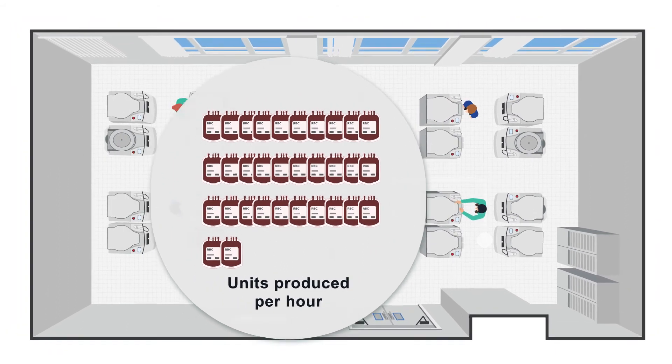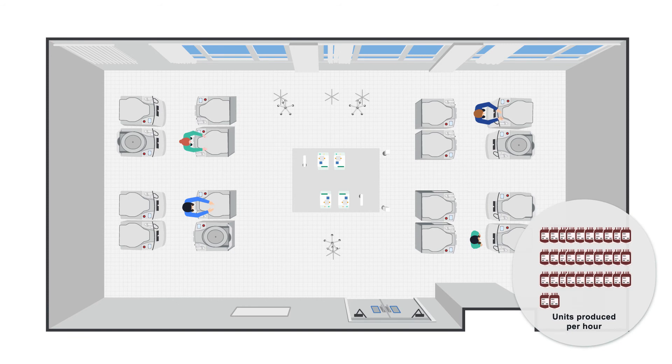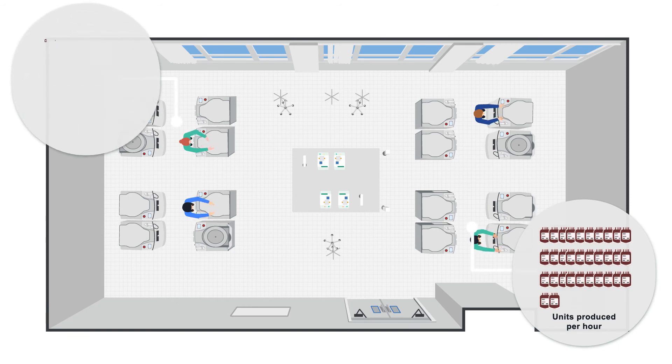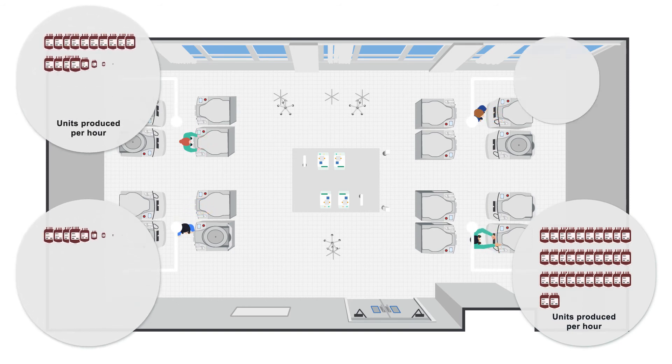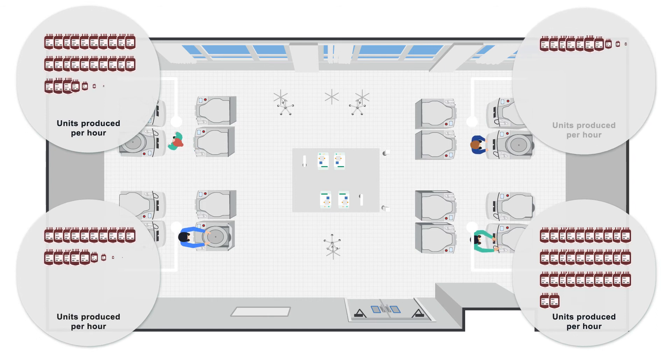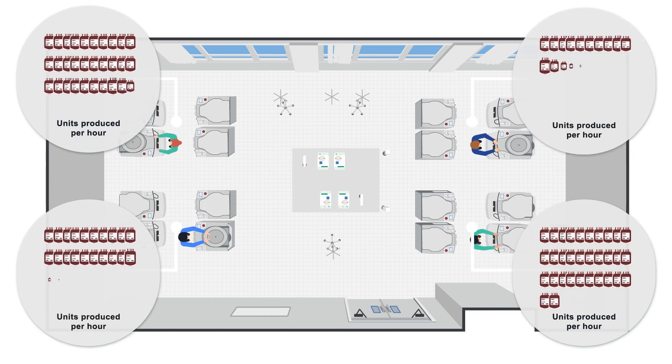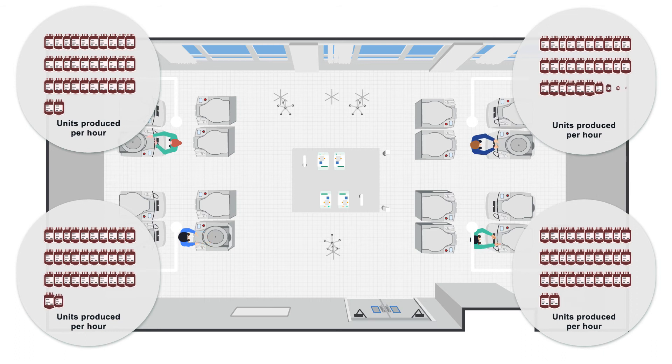For larger setups, we recommend expanding the pod number. In this case, four operators will handle four pods. With each Revios device processing eight whole blood units per hour, 16 of these devices will generate 128 red blood cell, plasma, and platelet units.